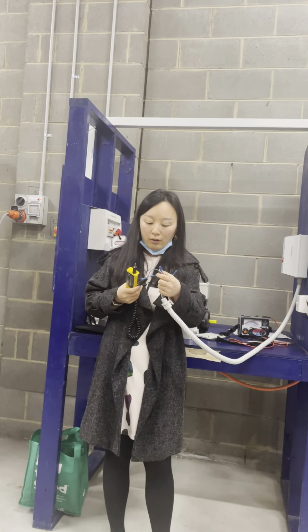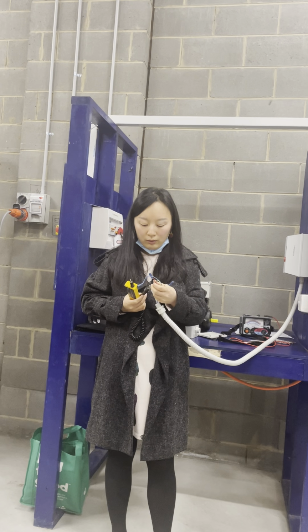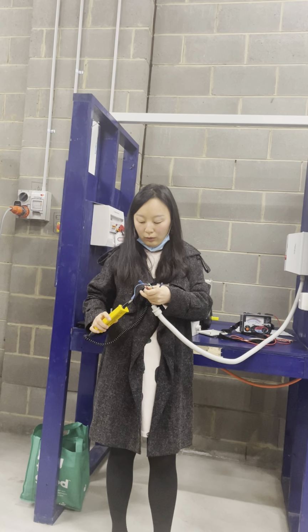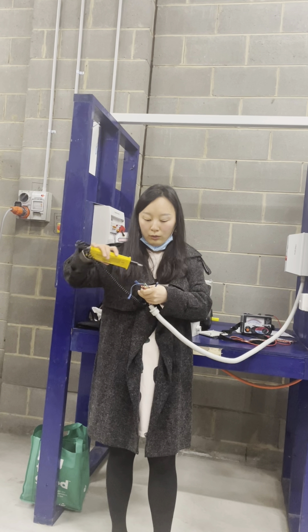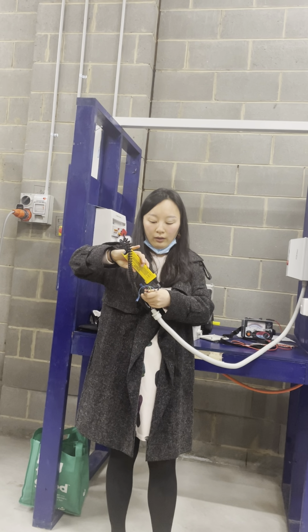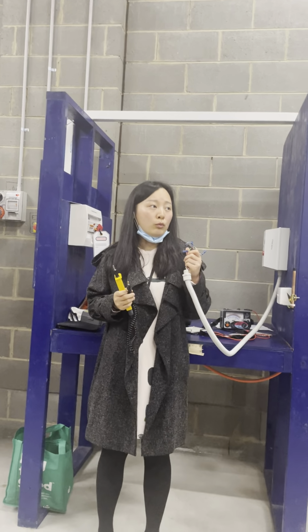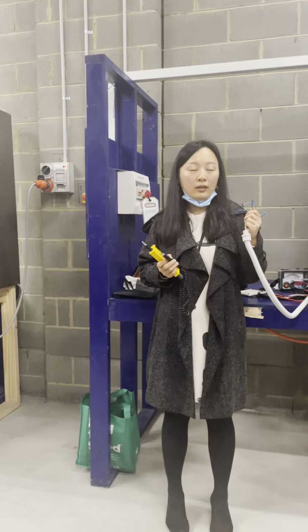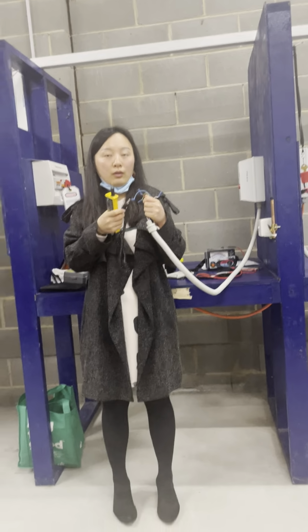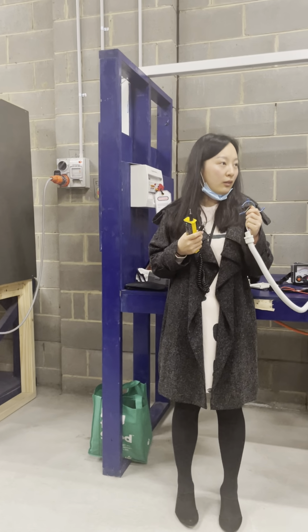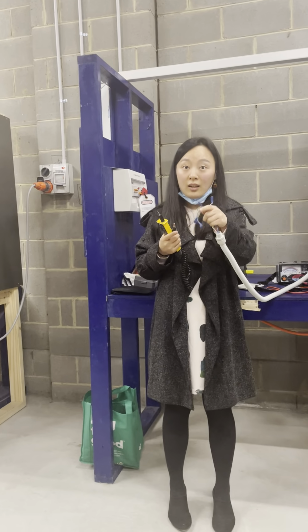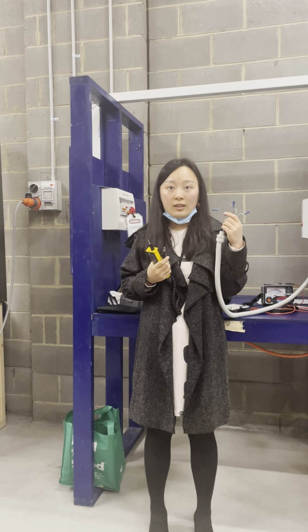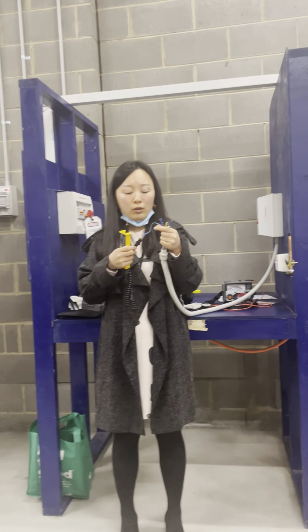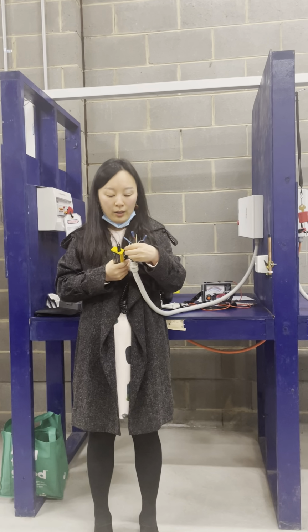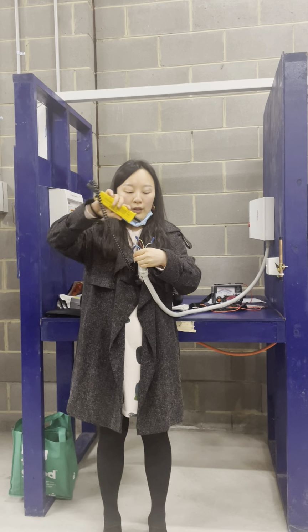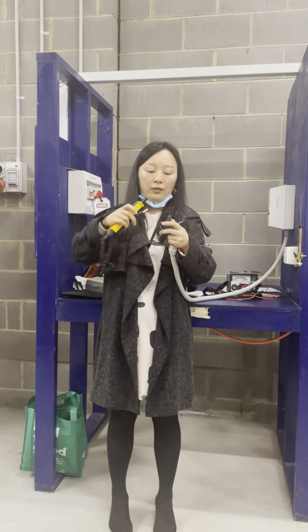So now I'm checking between earth to phase 1, 2, 3. Now someone tell me, do I need to do more tests? I've checked between earth, is that required? Not required. Between the phases, correct, yes. This is 3 phase, you must do between phases as well, and that's worth 20 marks. So you need to check between phase 1 to phase 2, phase 1 to phase 3, and then phase 2 to phase 3.